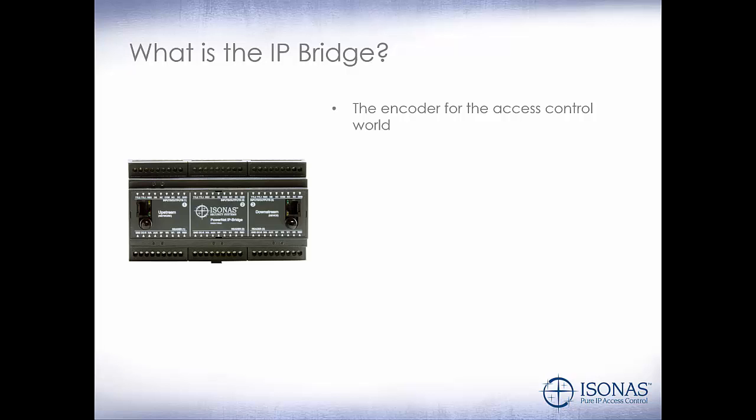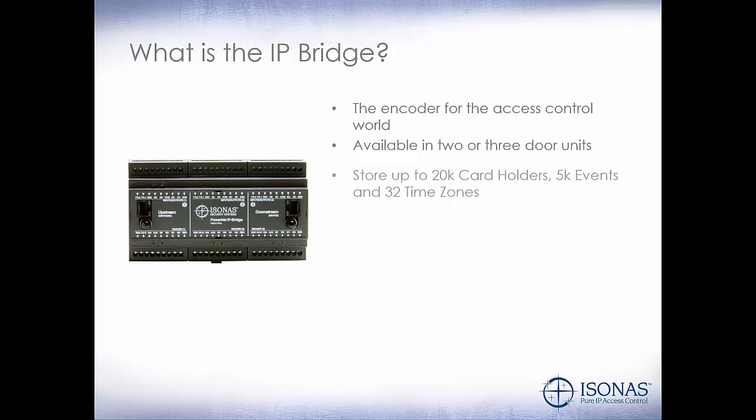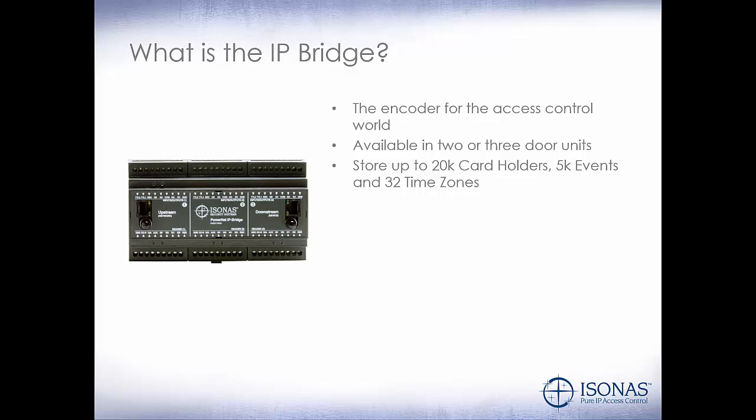So first off, what is the IP Bridge? The IP Bridge is the encoder for the access control world. It's available in two or three door units. It can store up to 20,000 cardholders, 5,000 events, and 32 time zones. Local decision making, the same as the PowerNet. DIN rail mountable for easy mounting.